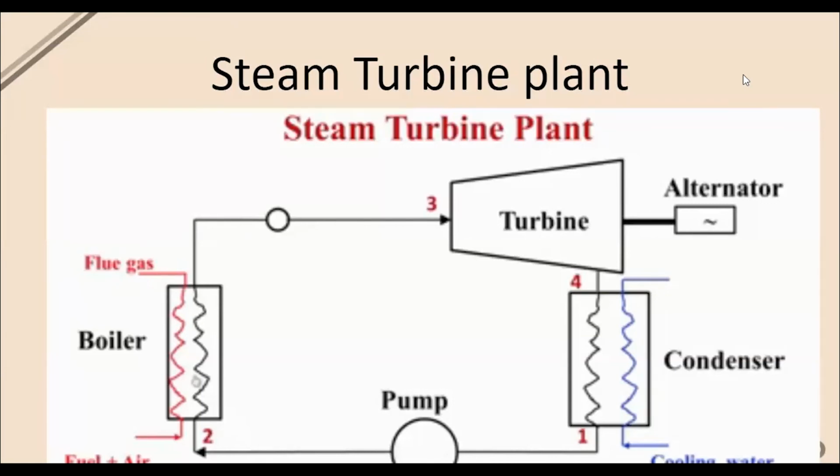And the steam is passed through the turbine at high pressure. The working fluid, which is steam, could be anywhere between 300 or 400 or 550 degrees centigrade and is passed through this turbine. Generally in bar, 165 bar or 170 bar is the highest high pressure that can be used, reduced to high velocity gas, and there will be a governing system which will govern the steam into the steam turbine.